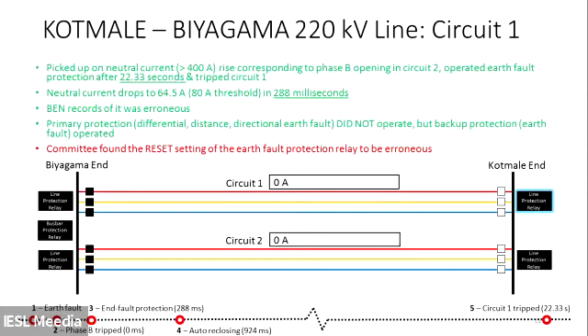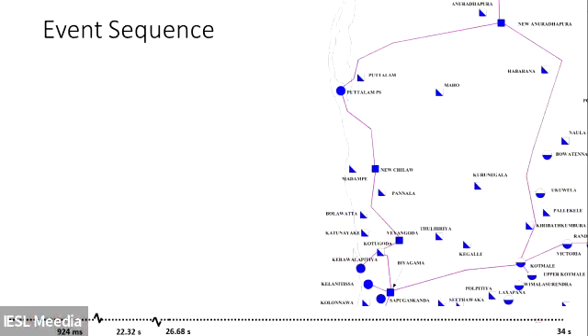Now, first, circuit 1 and circuit 2 on the Kotmale-Biyagama transmission line. Once that happened, the current, which was 750 each previously, became 0, and that path was no more available. The only route for the power to flow in a hydro-max scenario is via Kotmale, New Anuradhapura, and that side. On that particular day, in that 170 kilometer long double circuit, circuit 1 was out for some other project work, so only circuit 2 was there. I will come to that towards the end.